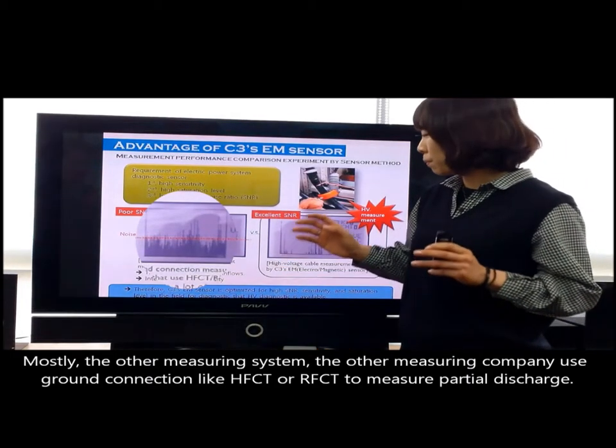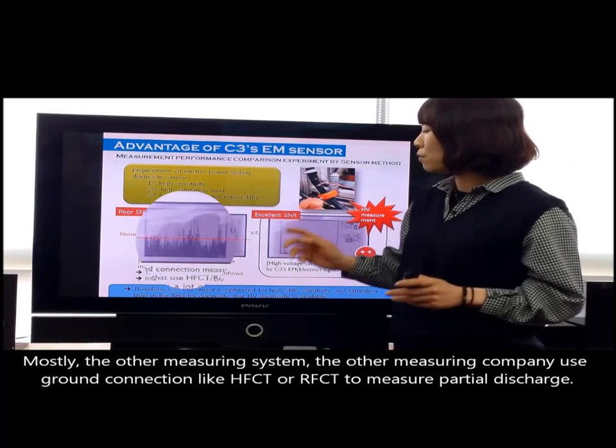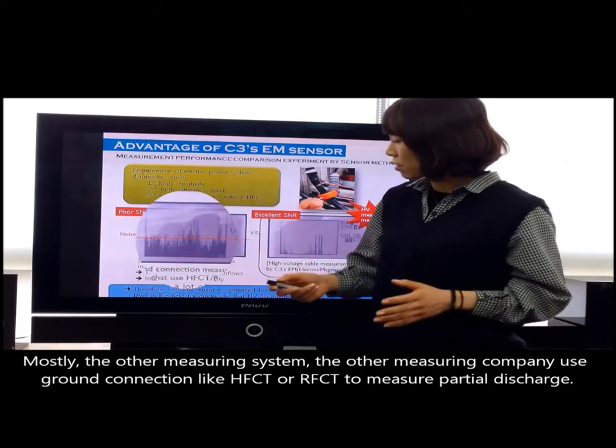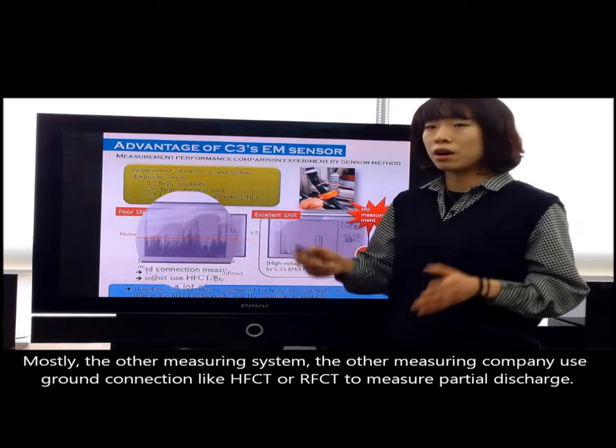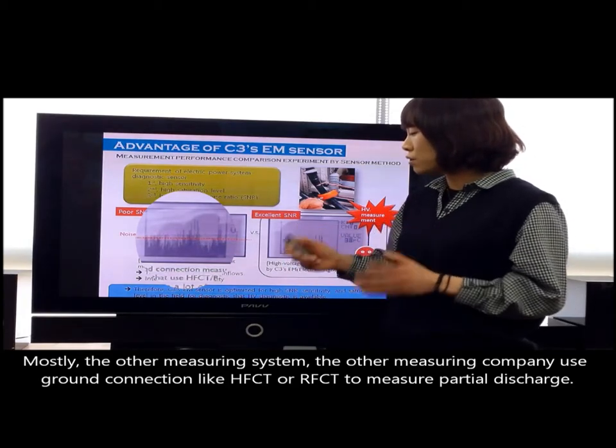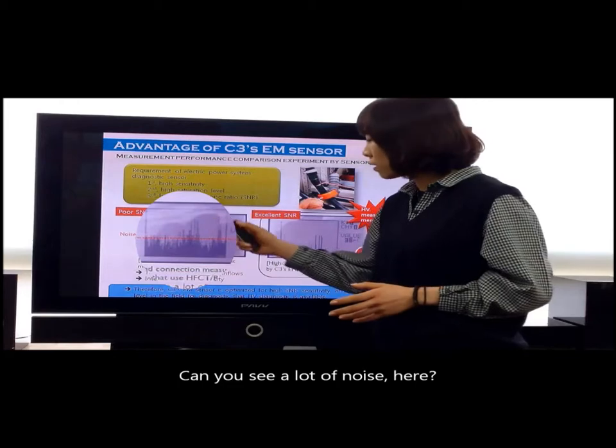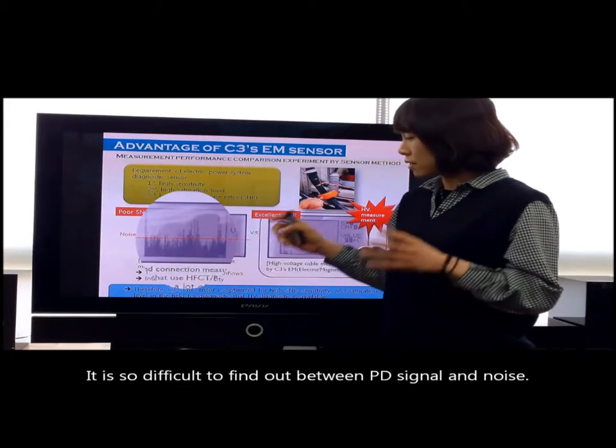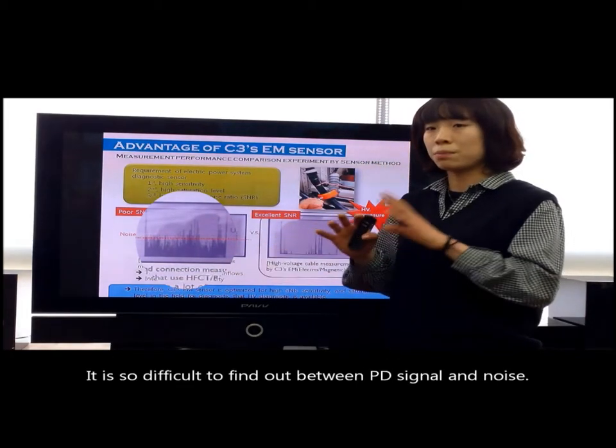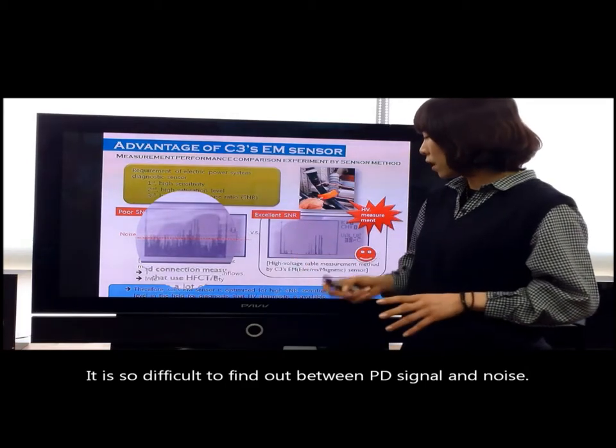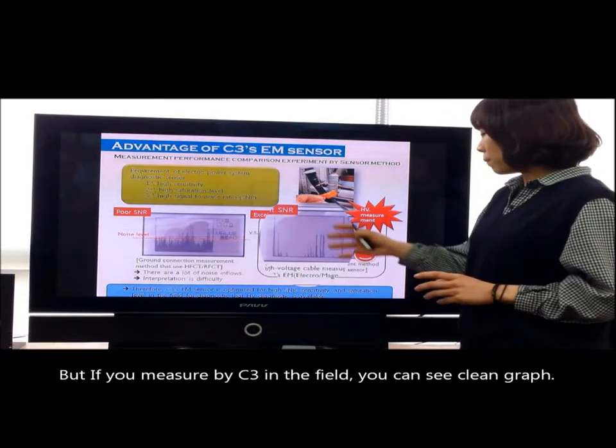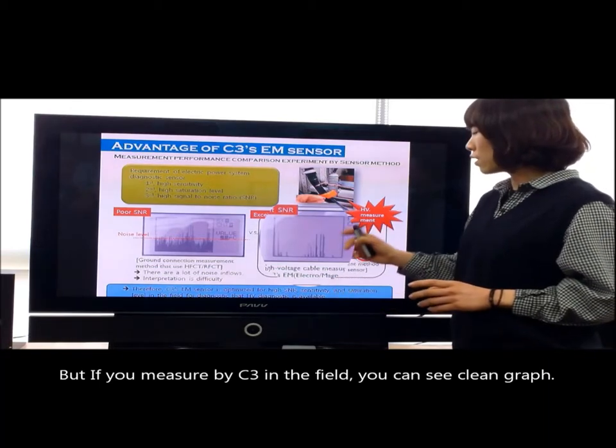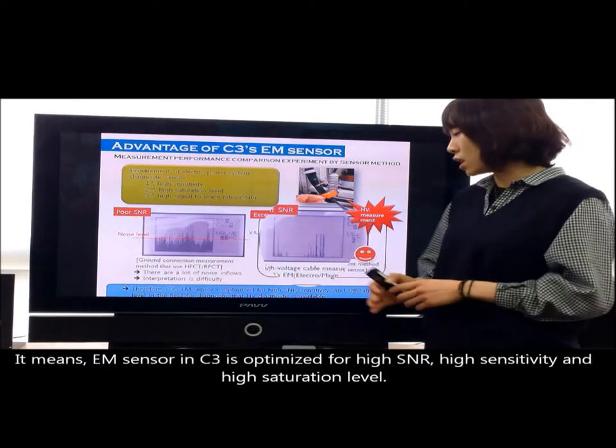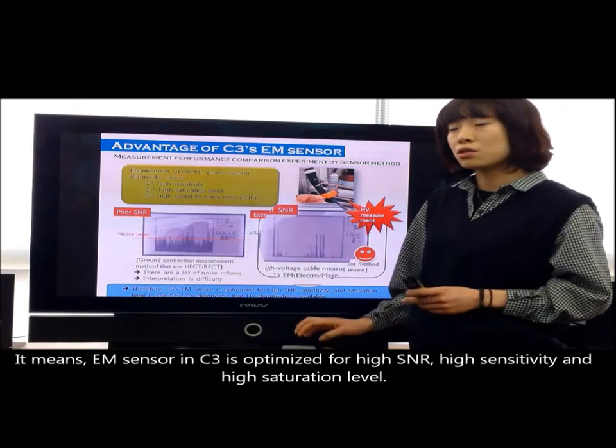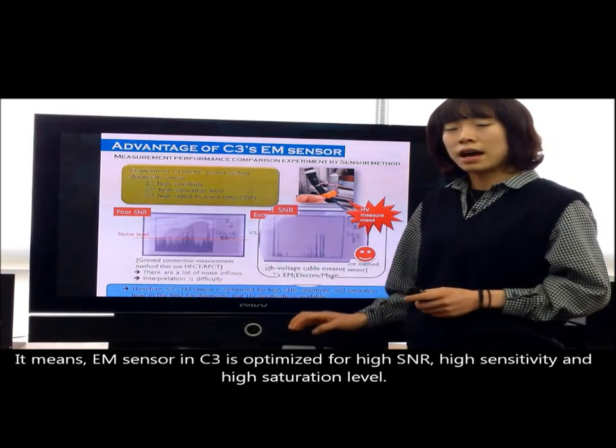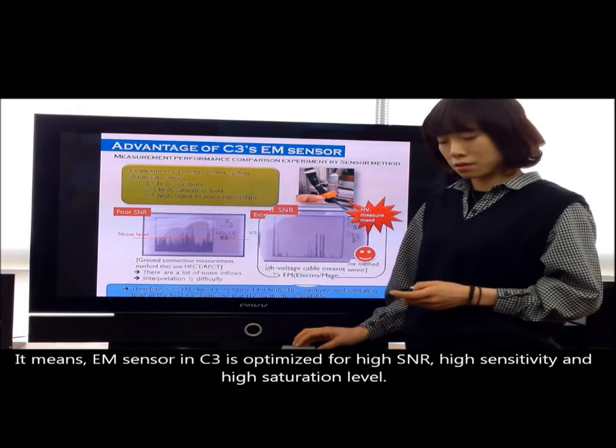Mostly the other measuring companies use ground connection like HFCT or RFCT to measure partial discharge. Can you see a lot of noise here? It is so difficult to distinguish between PD signal and noise. But if you measure by C3 in the field, you can see the clean graph. It means the EM sensor in C3 is optimized for high SNR, high sensitivity, and high saturation level.